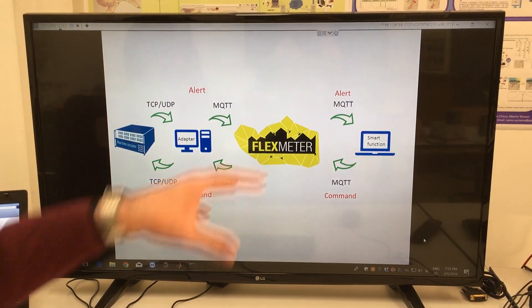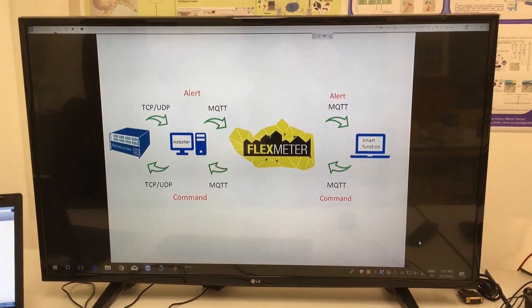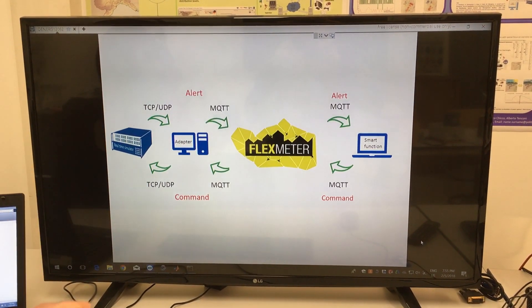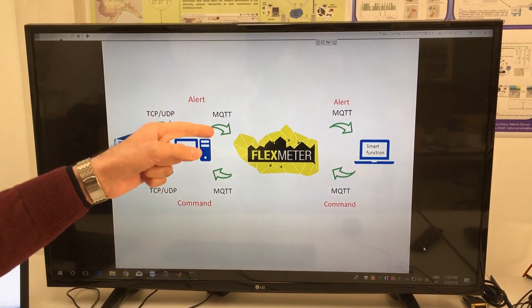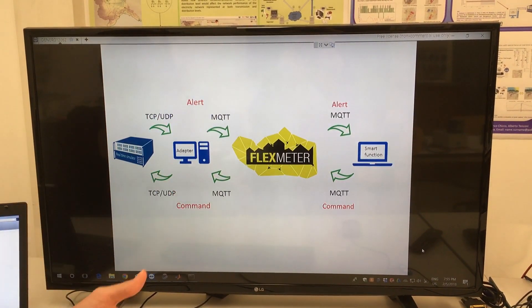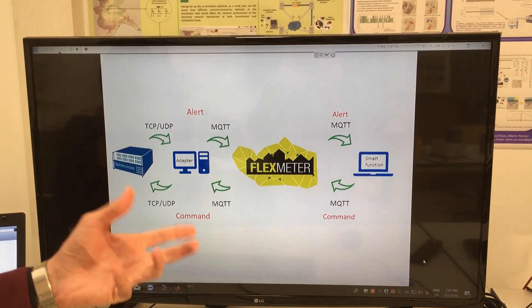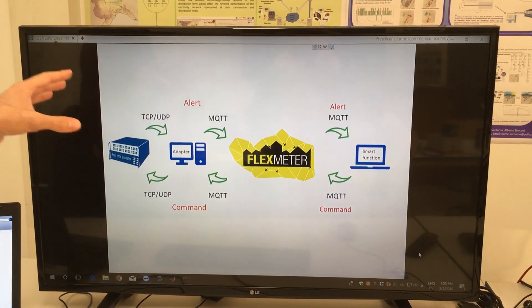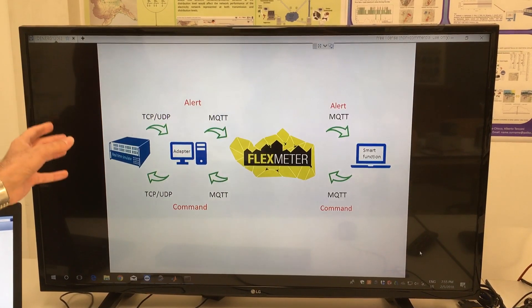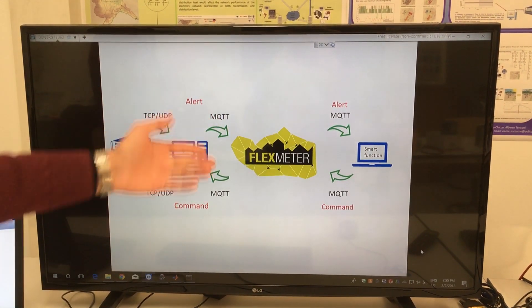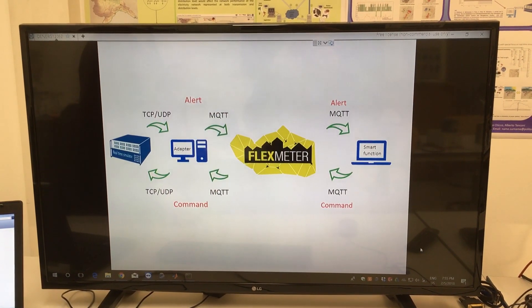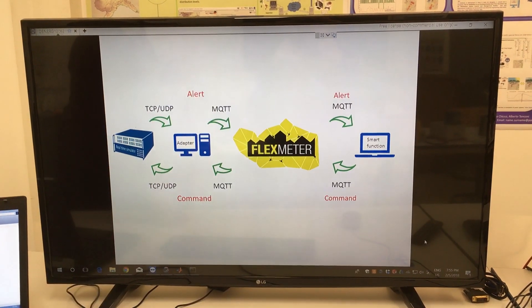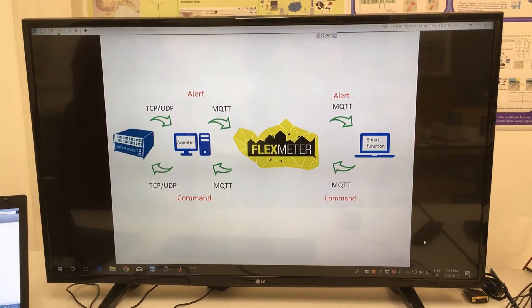In our case, this smart function is FDIR, which is similar to the fault detection algorithm. But in the fault detection algorithm, we retrieve measurements from the smart meters in the system and pass them to the algorithm to locate the fault. Here, FDIR takes actions in order to isolate and also restore the system. The actions rely on alerts retrieved from the system. So once the fault occurs, circuit breakers — through the IED — send alerts into the FlexMeter platform and eventually to the FDIR. FDIR then sends commands to the reclosers, normally open switches, or any other actuators in the system in order to isolate and restore the system.